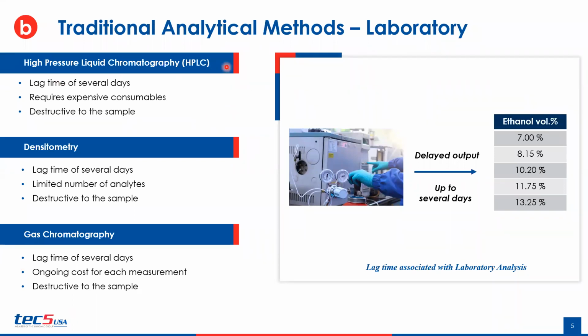And then taking a closer look at the details, high pressure liquid chromatography often requires expensive consumables such as organic chemicals, which can, of course, add up per measurement each time you require it. In the case of densitometry, this is a well-known method for ethanol detection, but it is limited in the number of analytes that it can be performed for. So again, this is ideal for ethanol, but if there are additional parameters that are required, the end user will have to find the appropriate laboratory to perform those measurements.